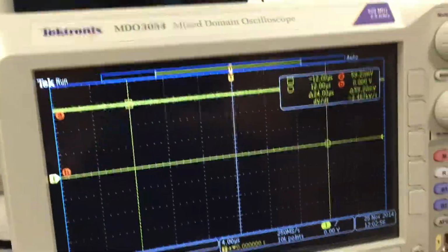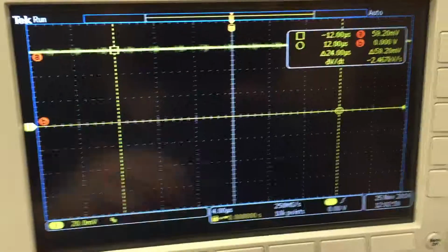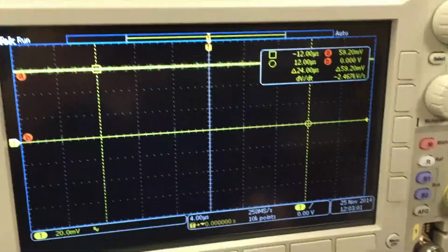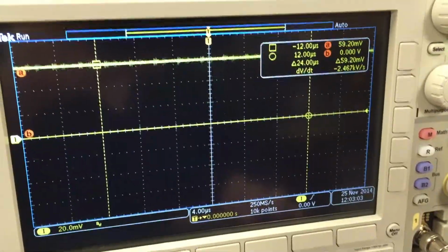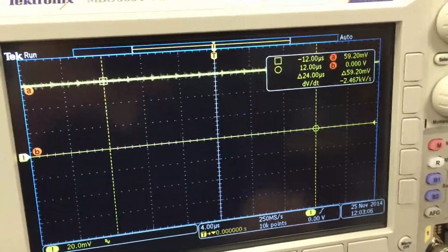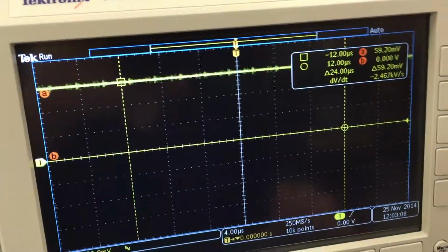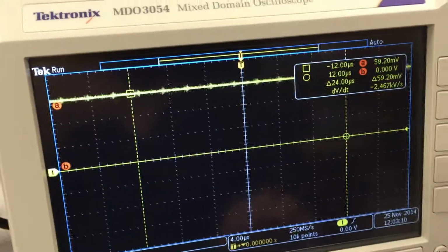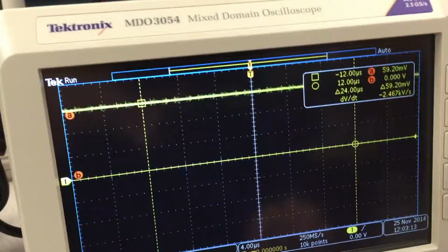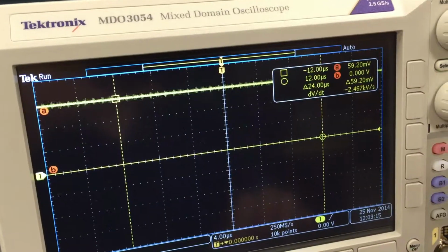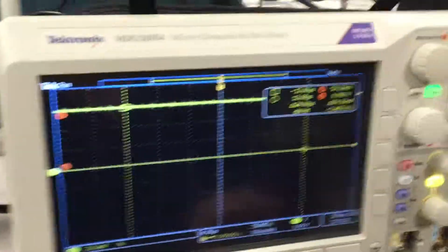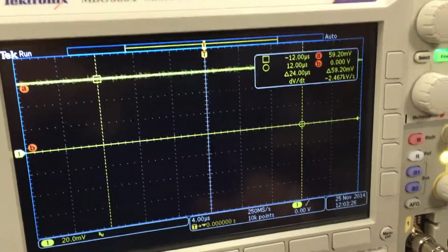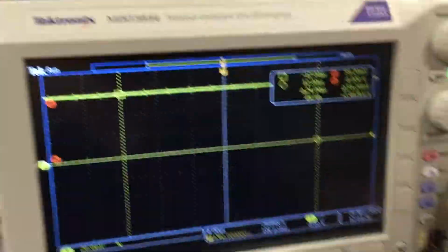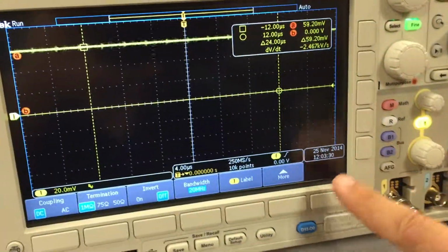we're measuring about 59.2 millivolts. So to do that conversion, we need to know, to calibrate the scope, how many millivolts per amp this probe is generating. So we'll take our 59.2 and divide that by 6.013, which is about now. And we end up with 9.845 millivolts per amp.